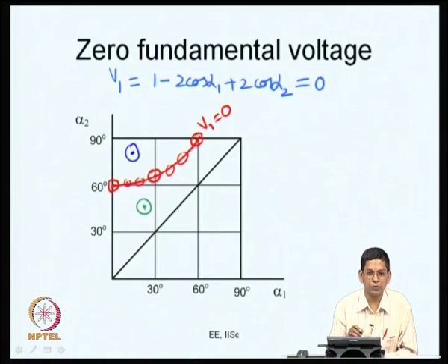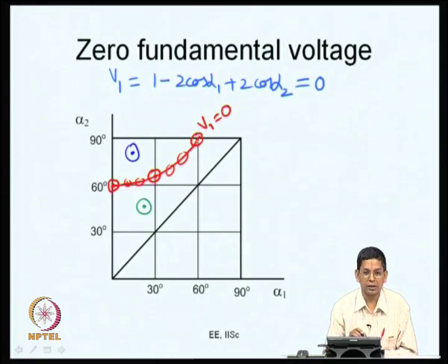So, at omega t is equal to 0, the fundamental will have a positive 0 crossing, whereas in the blue case the fundamental will have a negative 0 crossing, and so this is the line along which you have 0 fundamental voltage now. So, let us say you want 0 fundamental voltage, it is slightly funny, I would like to clarify this. In most open loop V/f drives, you may not come to 0 fundamental voltage at all. You may start with some minimum fundamental voltage, it may be 2%, 3%, 5% or whatever it could be, it is not going to be 0 fundamental voltage. But there are closed loop situations where you may want 0 fundamental voltage to be applied or certain small amount of fundamental voltage to be applied, that is a different point now.